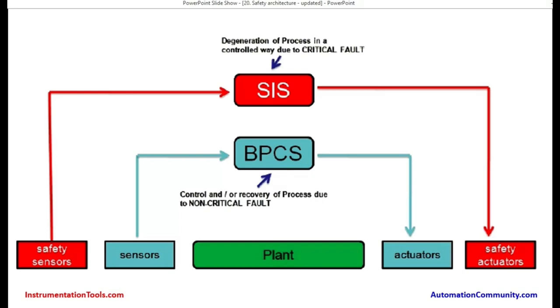Likewise, it can go to low pressure or low flow as another scenario. The operator may be required to take action to close a manual valve. If there is a failure or the manual valve does not work properly for whatever reason, it goes to the next level switch or level transmitter, which gives a signal — a safety-type sensor gives a signal to the safety instrumented system. The SIS has a programmed logic built inside during the engineering stage of the project, and will give a command to close the safety actuator. This is a hazardous situation wherein the safety instrumented system is acting to close the actuator, causing a controlled degeneration of the process due to a critical fault.